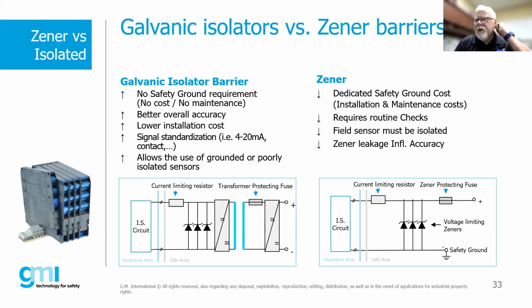We do have those routine checks. The field sensor must be isolated. There is an issue with Zener leakage, so Zeners over time can actually change, and that can affect the accuracy of these Zener diodes. That's not terribly uncommon. It's not a common problem, but it does happen over time. And that's another reason why we have redundant Zener barriers on the inside of these products.